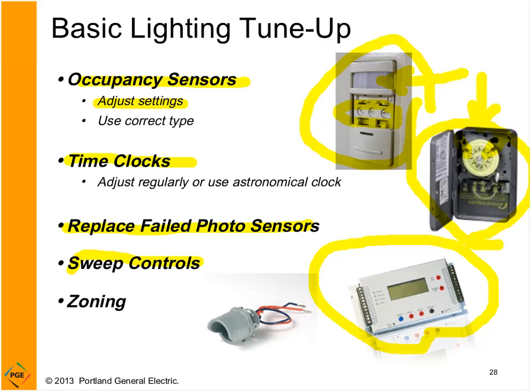The thing that you want to think about, though, is if you have sweep controls, you probably want to institute multiple sweeps. Because what happens at 7 o'clock if somebody's still in their office and the lights get swept off? Well, that occupant will end up turning their lights back on and maybe several other lights just to make sure that they feel comfortable and safe in the work environment, they can get their work done. So that's why you probably want to sweep the lights off again at 9 o'clock and then maybe again at 11 o'clock, just to make sure that you get those stragglers out of the building and you get your lights turned off as soon as possible.